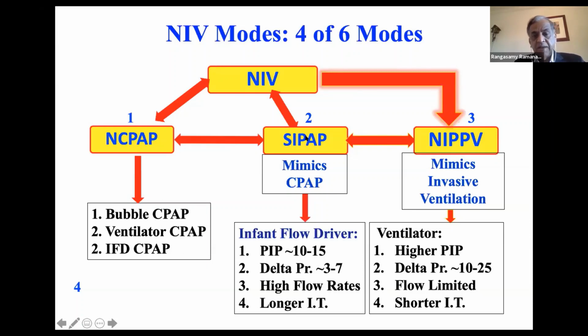Second mode is the Si-PAP. It basically mimics CPAP. It is just like CPAP because the infant flow driver generates a high pressure of about 10, maximum you can get 15 centimeters. PEEP, we usually keep at 5 or 6. So the delta pressure, PIP minus PEEP, is very little, somewhere around 3. For example, if you are 10/6, the delta pressure is 4, right? 12/6, the delta pressure is 6.